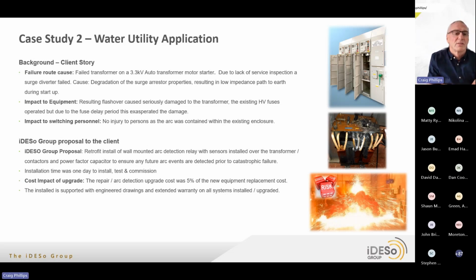Due to the fuses operating, there was a delay in the fuses operating, so that caused damage elsewhere in the enclosure. Luckily on this, there was no impact to personnel, as the arc was contained within the existing enclosure. Our systems are built to IEC 62271, which is the standard to ensure that there's no injuries to the operator, and all doors are held back. There's no parts of the switchgear being stressed and being projected towards the operator, and all explosive gases have to be marshalled away to the rear and upwards away from the operator.